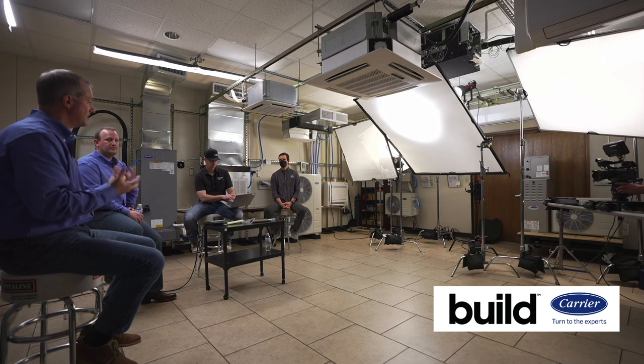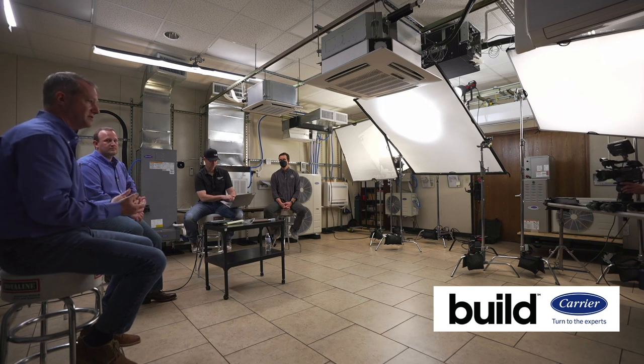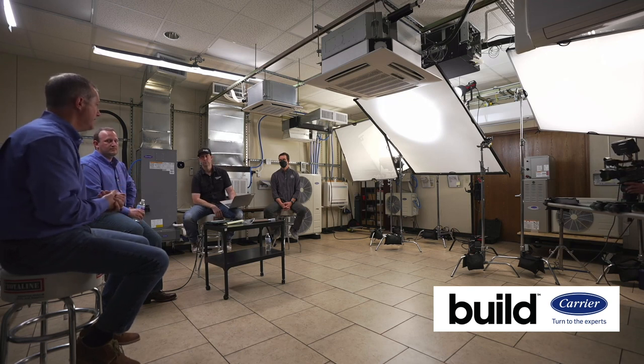Dual fuel hybrid combinations are absolutely embraced by us and available. You can have ductless outdoor units matched up to gas furnace indoor units. It just depends on what is best for that particular application. You can mix and match really any way you want. One cool thing about our equipment is we use a 24-volt interface to help the different systems communicate, but we retain the full variable speed nature of that inverter compressor. Nobody else can do that when you match up hybrid systems like that, so it's a really cool way to go.